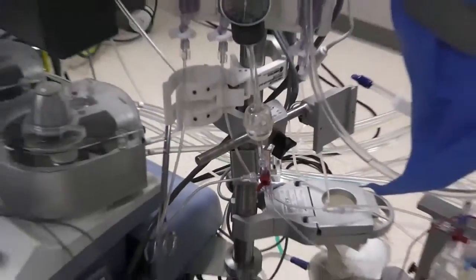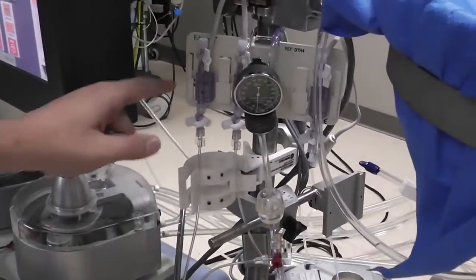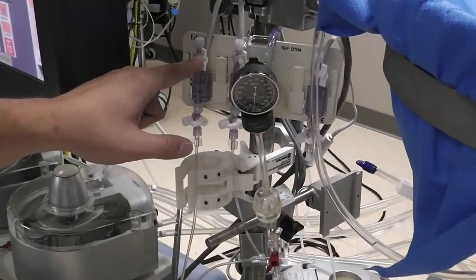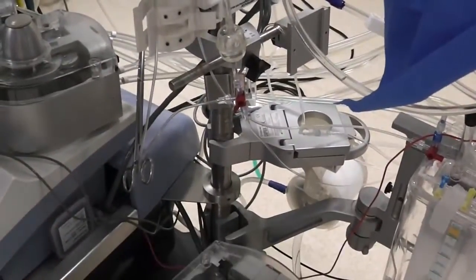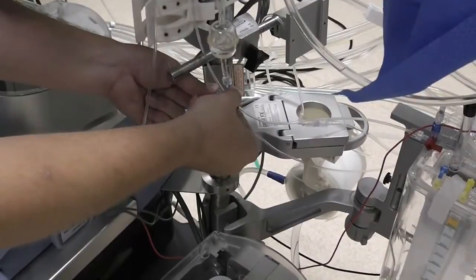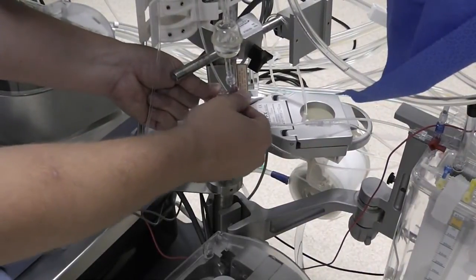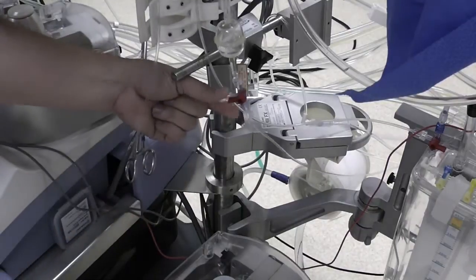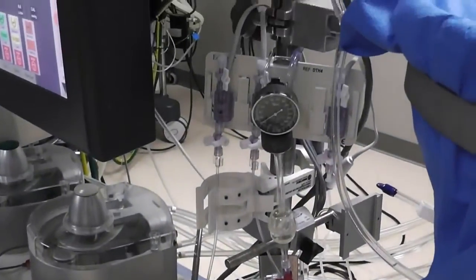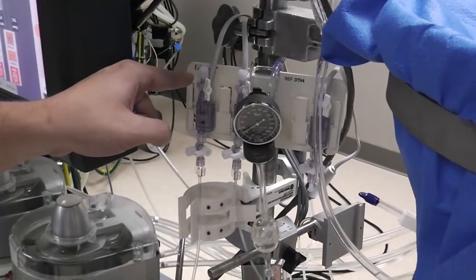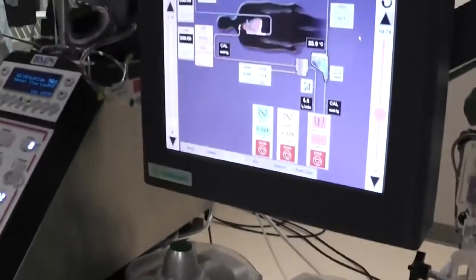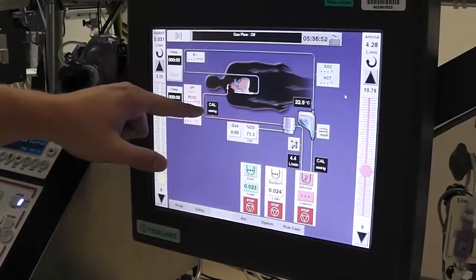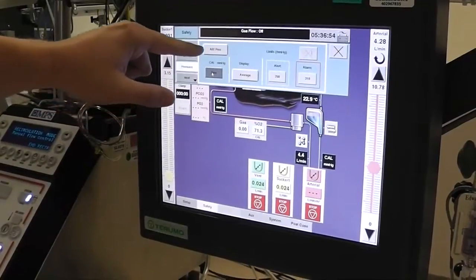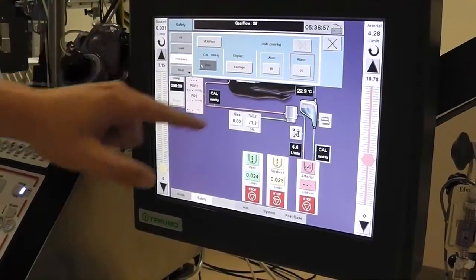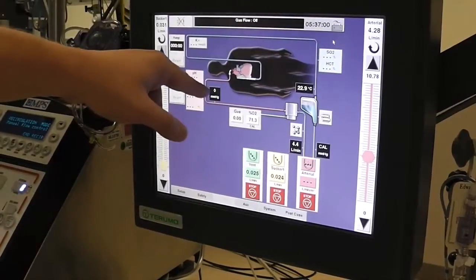Now you can do this any number of different ways here, but up on the pressure transducer you'll see that this is open. Down here we're going to open this line until we just see fluid coming out of the top of that stopcock. Then we're going to close that off. You probably can't see it, but there's just a tiny bubble of fluid up here on the transducer. We're going to come over to the pump here, hit cal on the arterial, 0. Then while we're here we can go venous right away and 0 that as well. Close that out, you'll see this read 0.